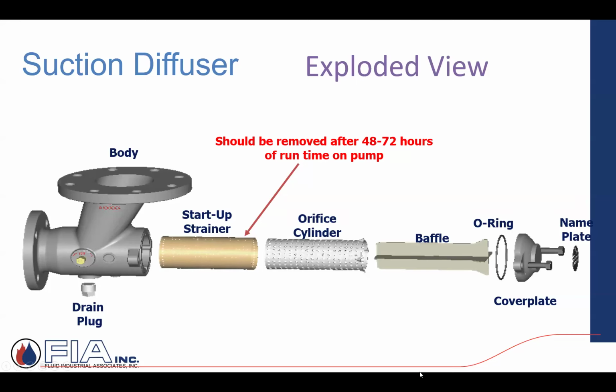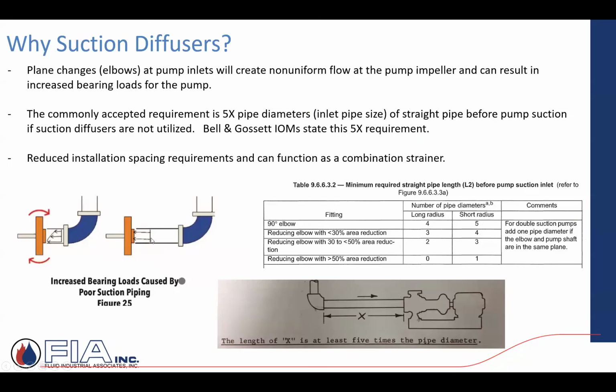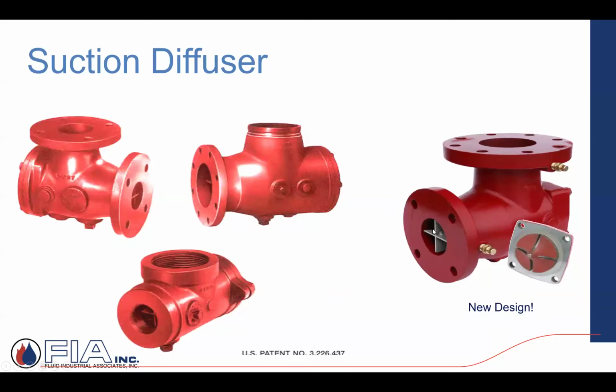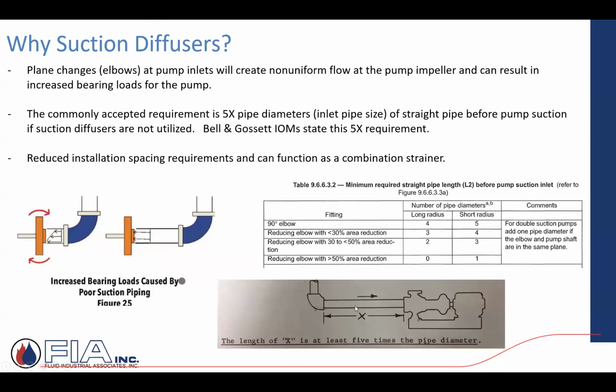So the suction diffuser, let me back up here. What it's doing is taking it through these vanes right here in that small little footprint. It's allowing that plane change to evenly load that impeller, and that vane will act as if you had provided that straight run of pipe. So it's a space saver. It's been around for a long time. Any type of end suction, almost always you're going to see that specified as part of the accessories on a base mounted pump.